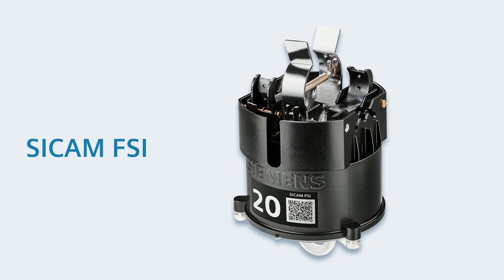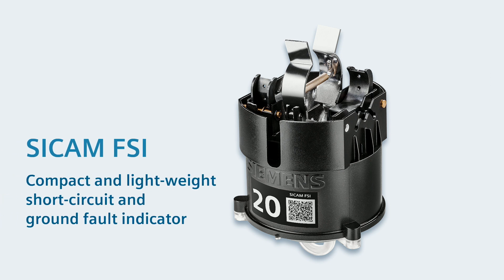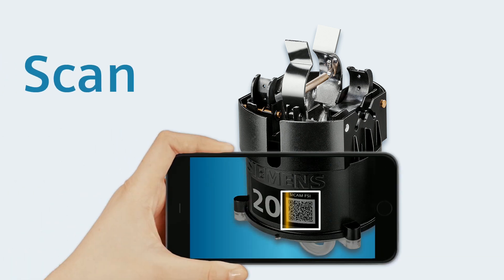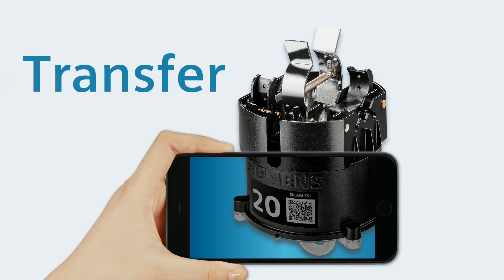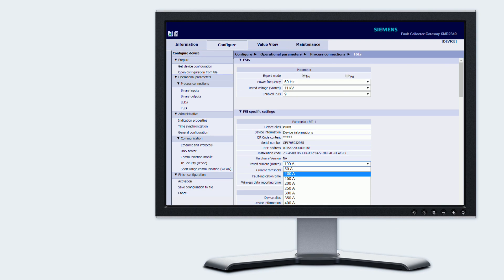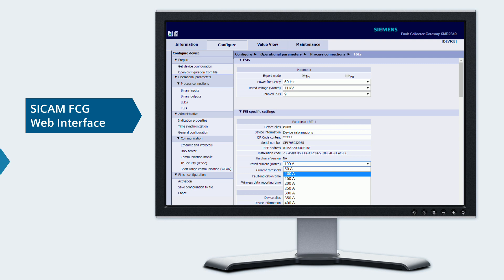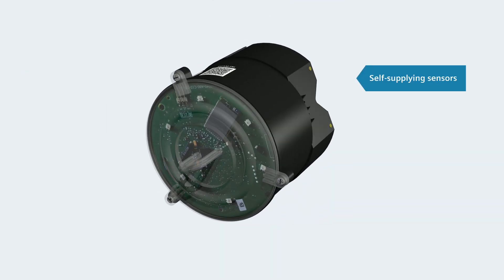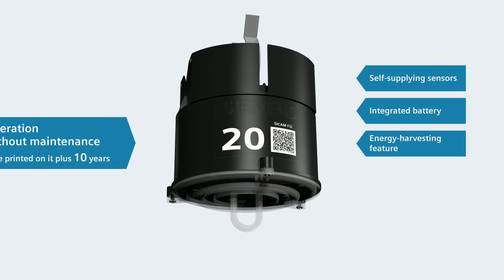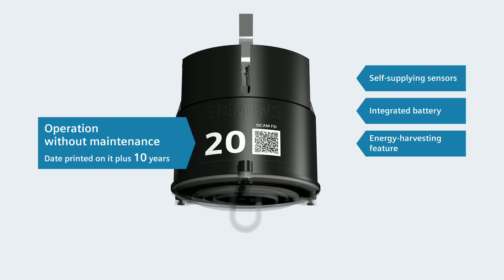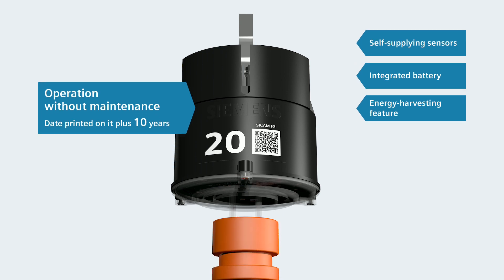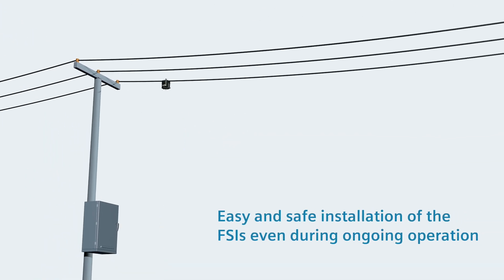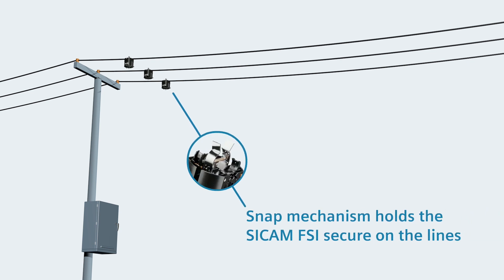With the SICAM FSI, you get a compact and lightweight short circuit and ground fault indicator. Before installation, you scan the QR code mounted on the housing. Transfer the scanned code to your PC, for example via email. Then use the SICAM FCG web interface to define the settings of the SICAM FSI with integrated communication. Thanks to the self-supplying sensors with integrated battery and energy harvesting feature, the SICAM FSI is ready for operation without further maintenance for about 10 years as of the date printed on it. Installation on the overhead line cable is done easily and safely using a hot stick with proper insulation even when the power supply is in operation. The snap mechanism on the top of the housing holds the SICAM FSI absolutely secure on the lines.